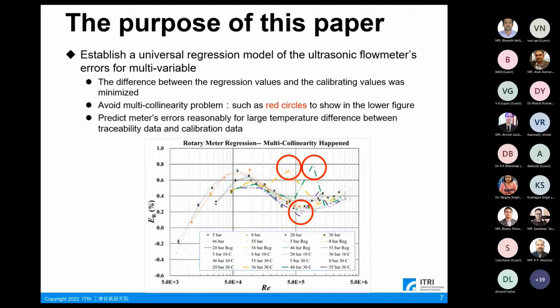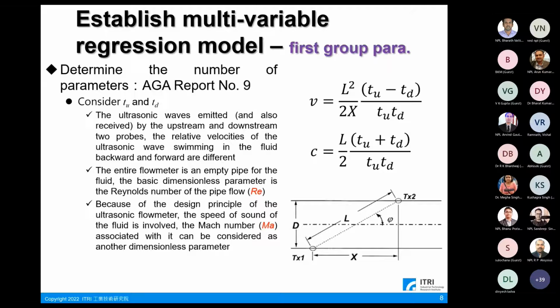The model should satisfy the following requirements. The difference between the regression values and the calibration values is minimized. It avoids the multi-collinearity problem, as shown by the red circles in the lower figure. It predicts meter errors reasonably for large temperature differences between the traceability data and the calibration data. As mentioned in the preface, when the flow standard is suitable for a wide range of pressure, temperature, and flow rate, the regression of the characteristic curve of the flow meter may have to consider multivariables. The approach of this paper was as follows. First of all, let's try to understand the principle of the ultrasonic meter.